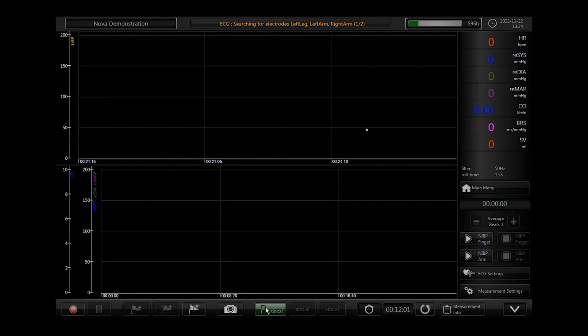The development and validation of the PhysioCal algorithm has been widely described in peer-reviewed literature. The algorithm in Finapres devices not only uses the amplitude, but also interprets the shape of the plethysmograph signal during periods of constant cuff pressure. By analyzing the plethysmograph signal at 2 or more pressure levels, the PhysioCal algorithm explores parts of the pressure-diameter relationship. Therefore, it is able to track the unloaded diameter of a finger artery, even if the smooth muscle tone changes. The periodic interruption of a finger blood pressure measurement with constant cuff pressure levels is referred to as PhysioCal.